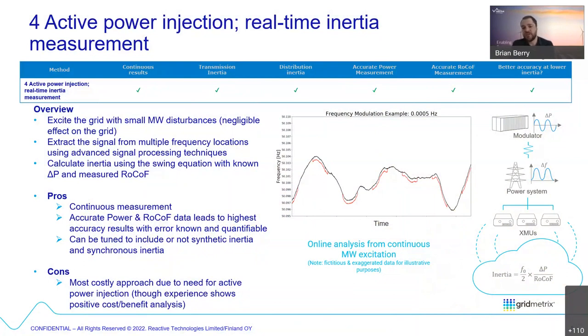The way we measure inertia is very similar to the concept of sonar. If you think of sonar sending out a pulse into the sea, and it measures the reflections, and that tells you how far away the seabed is, for example. We are creating perturbations in the power system. We are actually creating megawatt injections very purposefully into the power system. And the key thing here is that we do it with a periodic signal. So if you look at this picture here, which is just a hyperbole and exaggerated version, essentially we're creating a repeated micro frequency perturbation that we're able to measure from frequency measurements all around the grid.